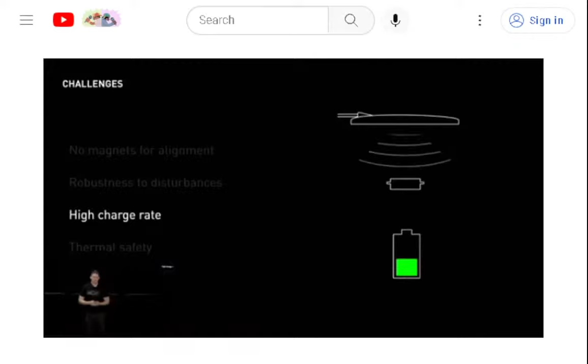However, unlike many consumer electronic devices, which can simply offer a physical connector, charging a fully implantable device poses several unique challenges. First, the system must operate over a wide charging volume without relying on magnets for perfect alignment. The system must be robust to disturbance and complete quickly so as not to be overly burdensome. However, most important is safety. In contact with brain tissue, the outer surface of the implant must not rise more than 2 degrees C.